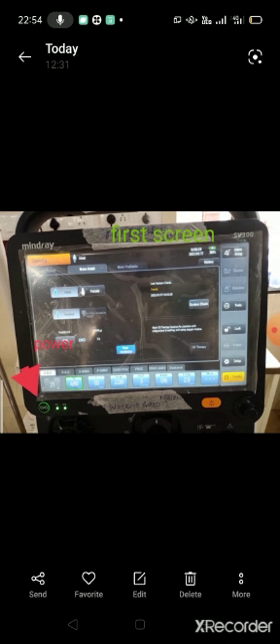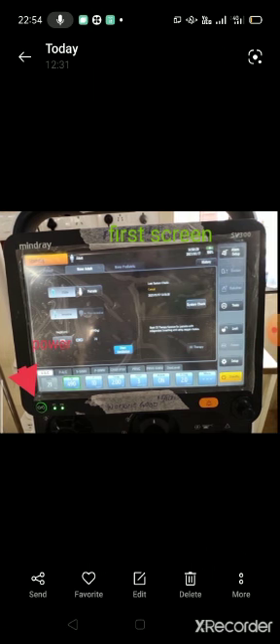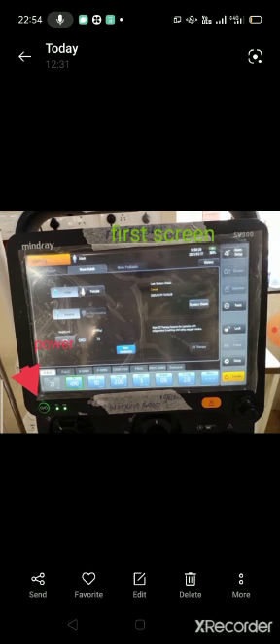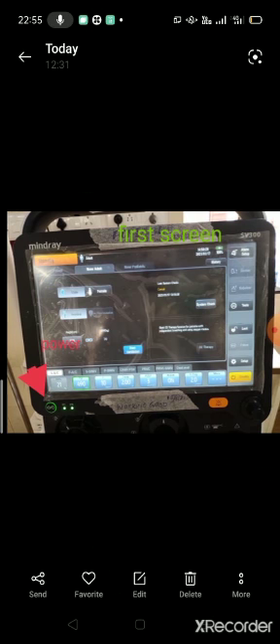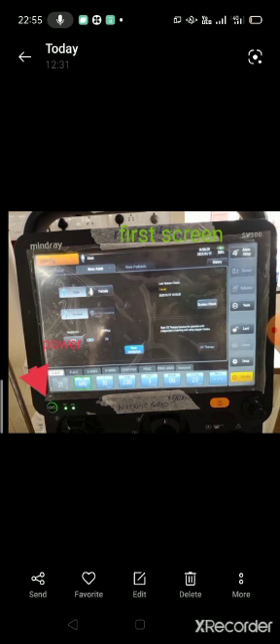And apart from this, you have to connect all the filters, everything that you are connecting to the patient, before doing the pre-use check, so that the compliance, dead space, and everything is calculated accordingly. So this system check or pre-use check is compulsory, as it ensures that the ventilator is working properly.